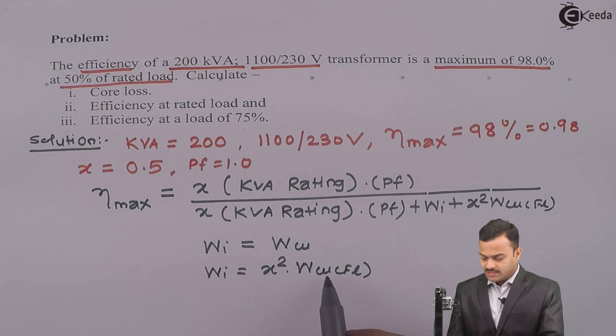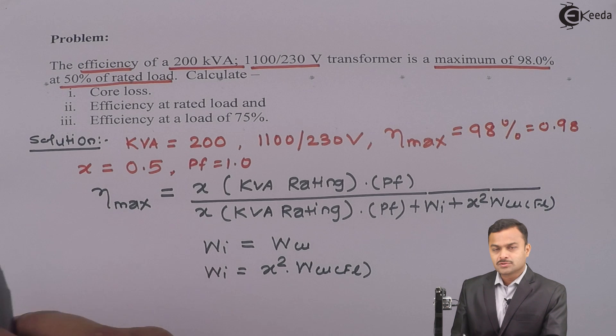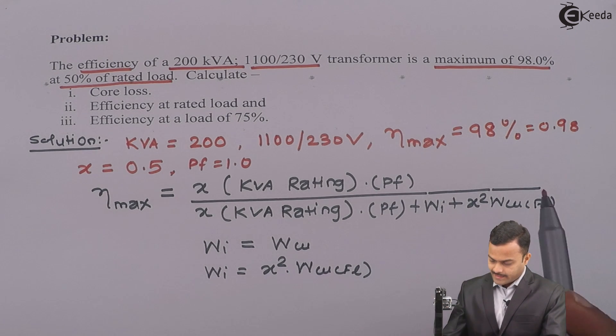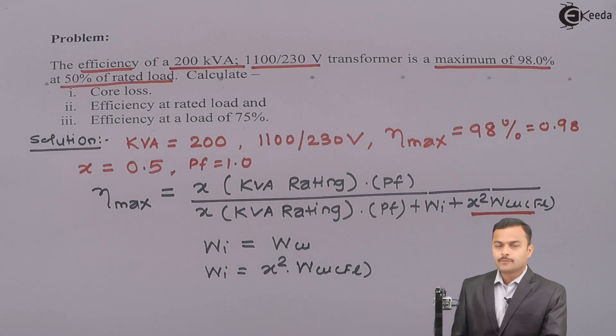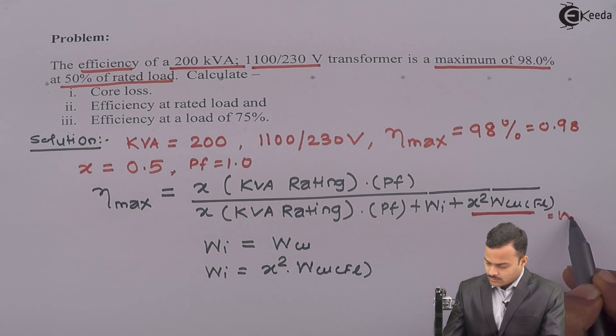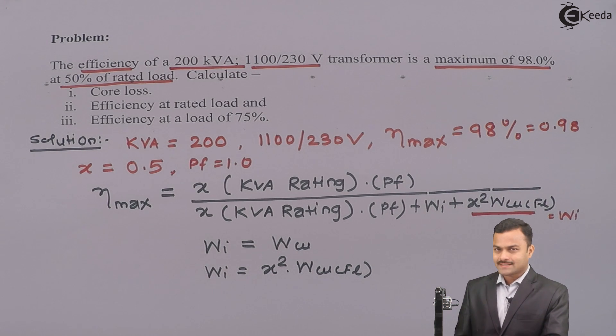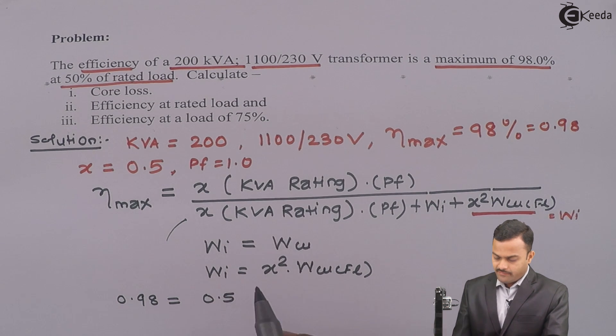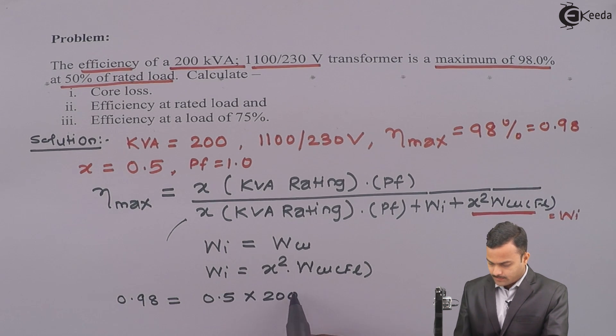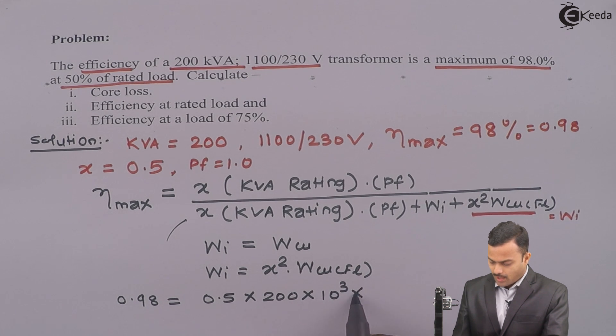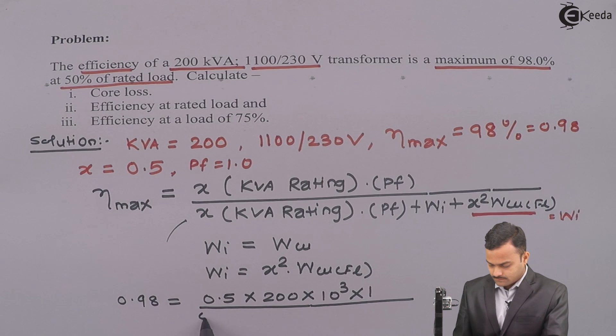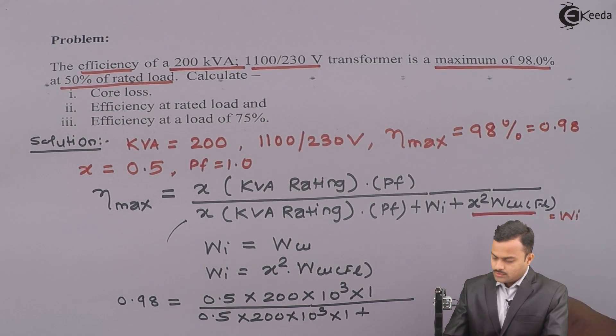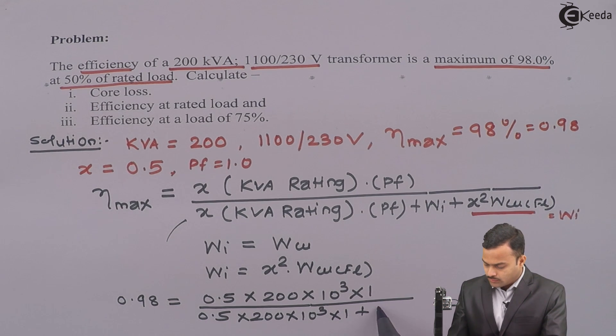How I am going to use this relationship over here? Let us substitute the values also. So instead of this X square WCUFL, I am going to write this equal to WI because efficiency is maximum the condition is WI equal to X square WCUFL. So efficiency maximum is 0.98, x is 0.5, kVA rating is 200, so it is 200 multiplied by 10 raised to 3 and power factor we assume unity.